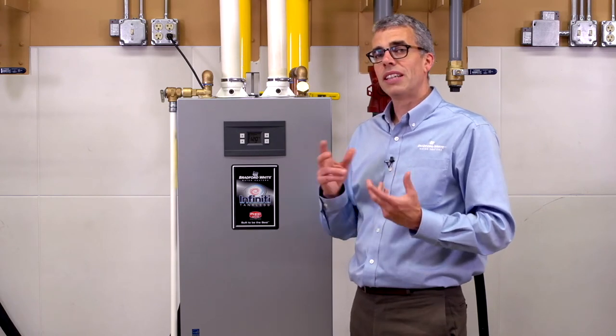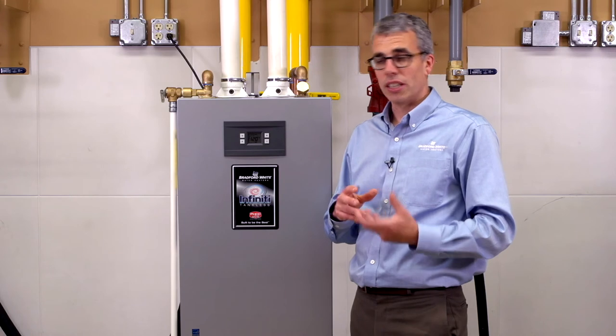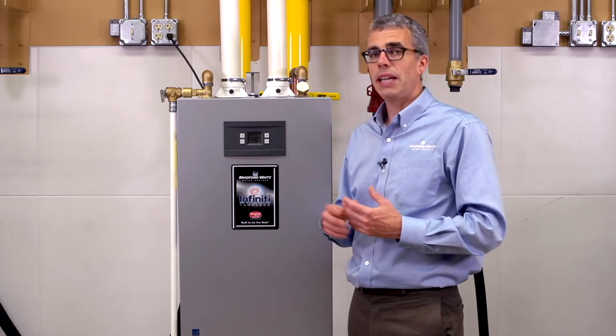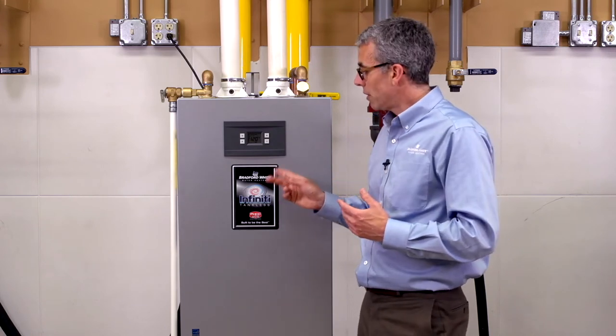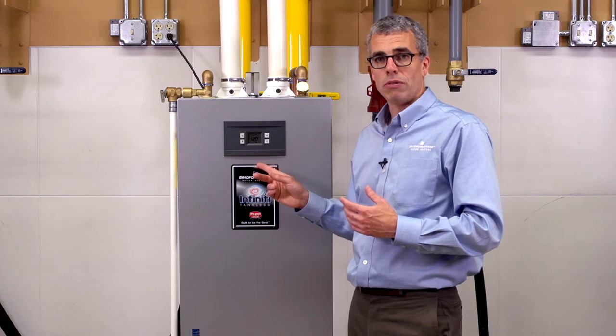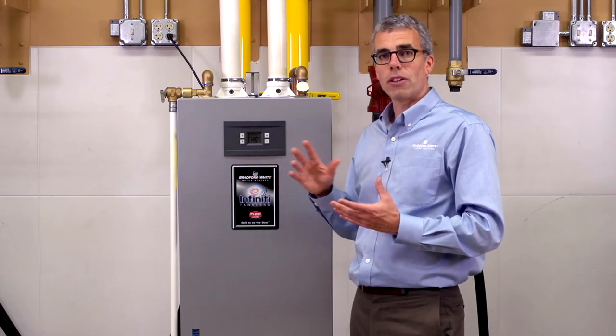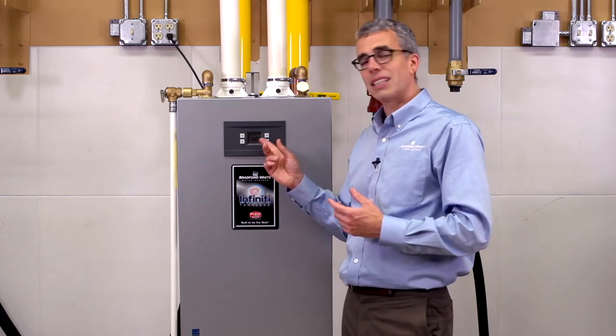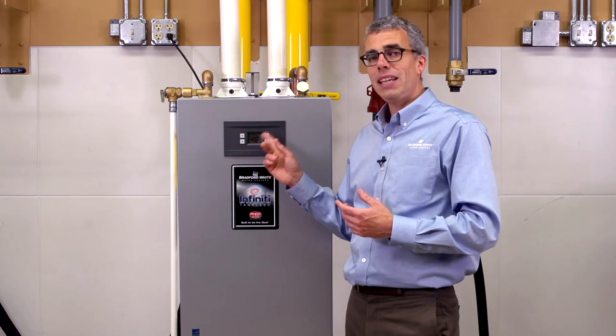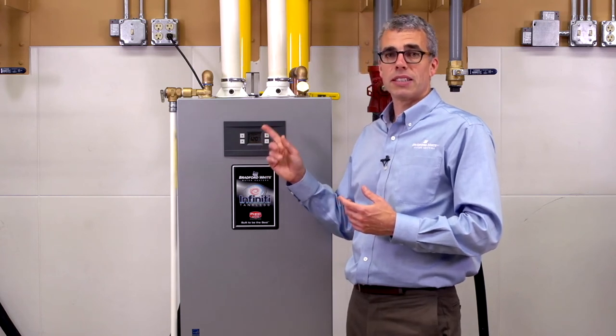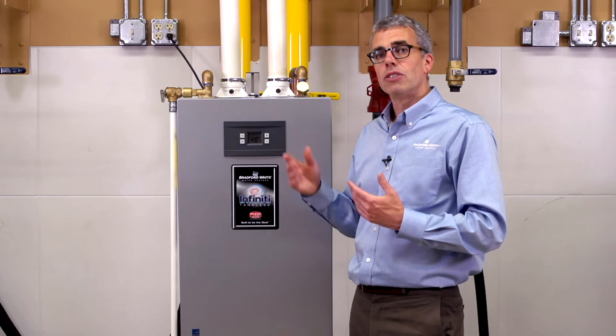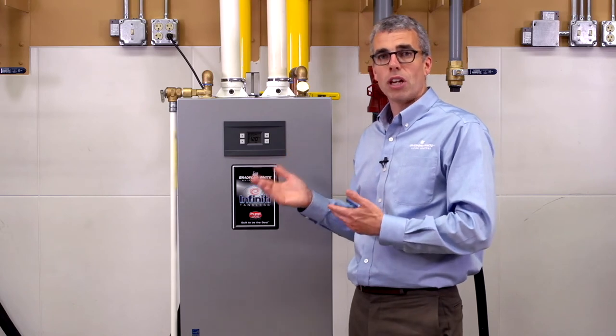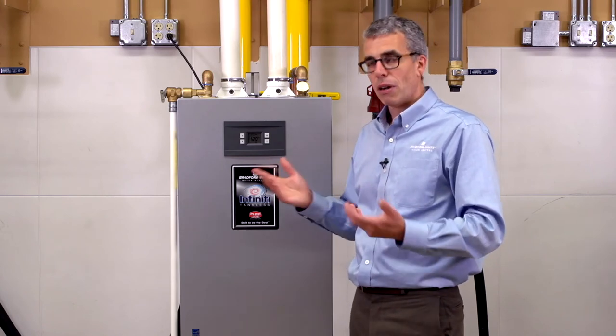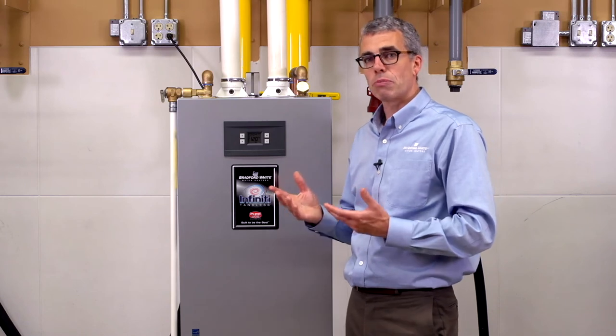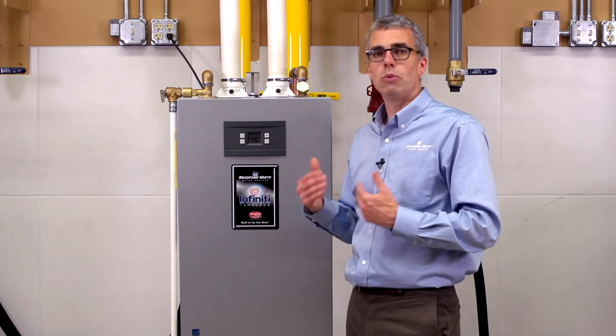If the problem persisted after the beginning of the installation and has always been an issue, that could be gas pressure. This unit is designed to restrict flow if it needs to throttle back on the flow rate in order to give you your selected temperature. It may need to do that in situations where it doesn't have adequate gas pressure, so it sacrifices your flow in order to give you temperature. The remedy in that situation is to correct the gas pressure problem, and the unit then will give you your flow back.